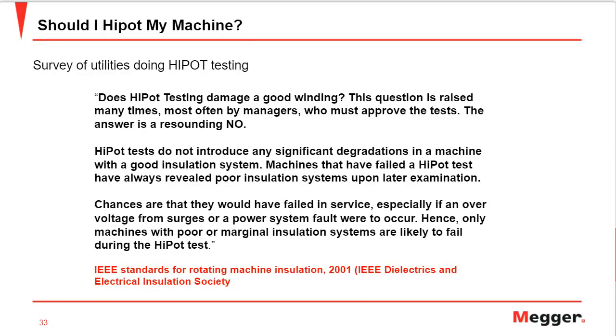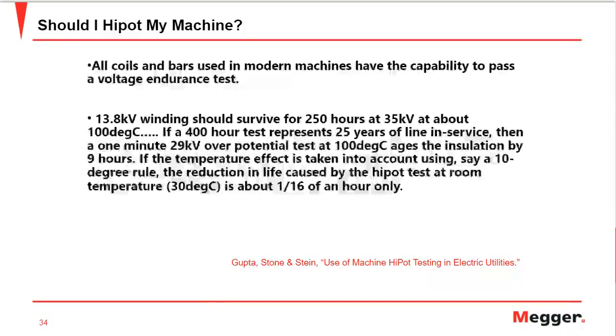Looking back at the standards, the test voltages we see are comparatively less than what the motor experiences during the initial starts, the voltage spikes or the VFD switchings. Another good article, or a good comparison, is from the book on machine HiPot testing in electric utilities. And this is a good comparison which can sum up why the DC HiPot test is not a destructive test on voltage, and why it is very important.